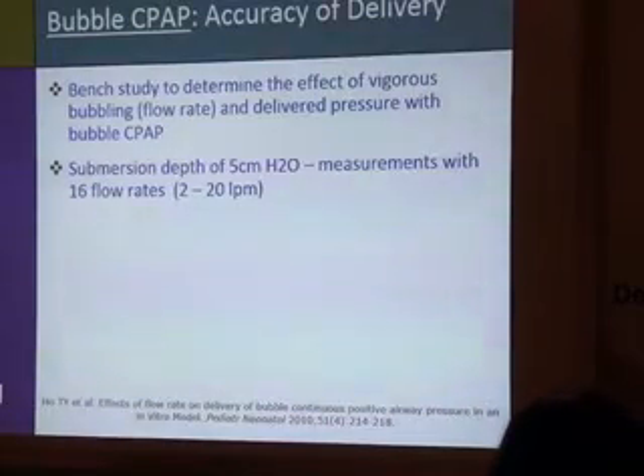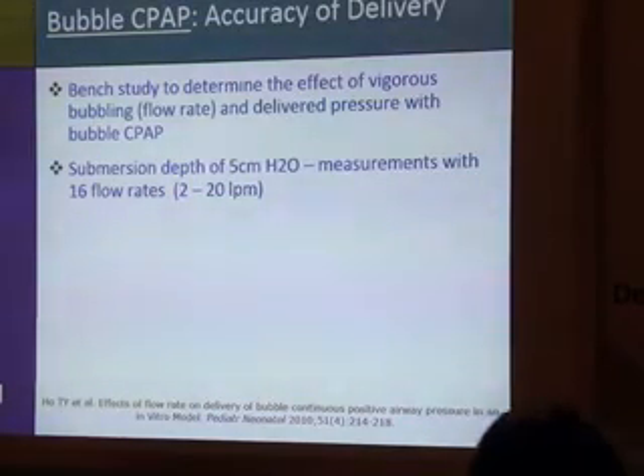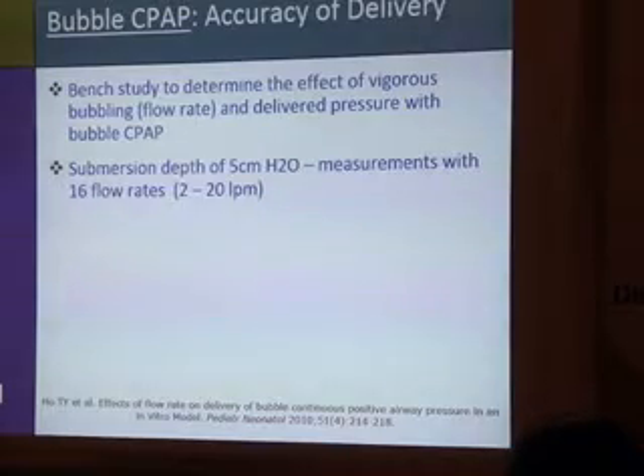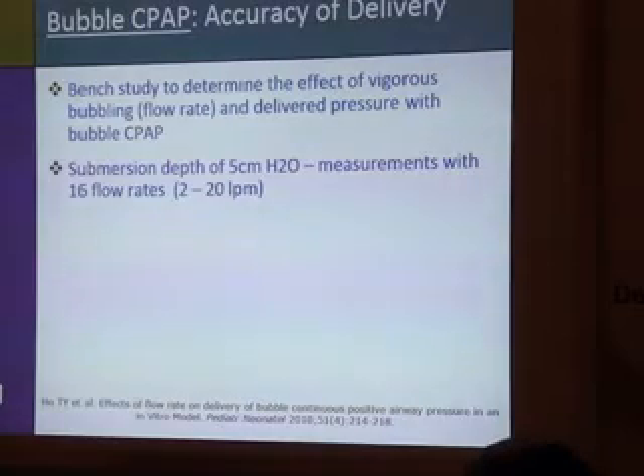The next study, published in 2010, was a bench study that looked at the accuracy of delivery of bubble CPAP. They looked at the effect of vigorous bubbling with the change in flow rate and how that also changed the pressure that was delivered. They used a submerged depth of 5 centimeters of water pressure. They kept that constant, and then they changed their flow rates over 16 different rates from 2 to 20 to see what the changes were.